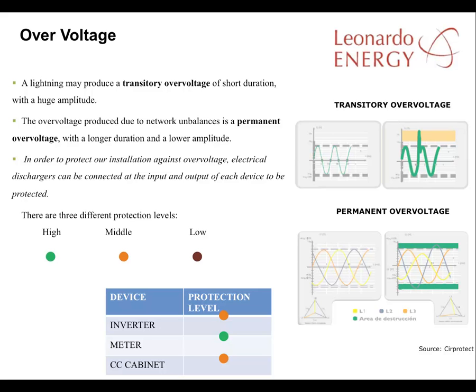To protect an installation against over-voltage, electrical dischargers should be connected at the input and output of each device needing protection. The inverter and control cables will meet a medium level of protection, while the meter will need high protection. The dangers here include lightning strikes that can produce short periods of transitory over-voltage with huge amplitudes. Network imbalances can result in permanent over-voltage with longer duration and lower amplitude.